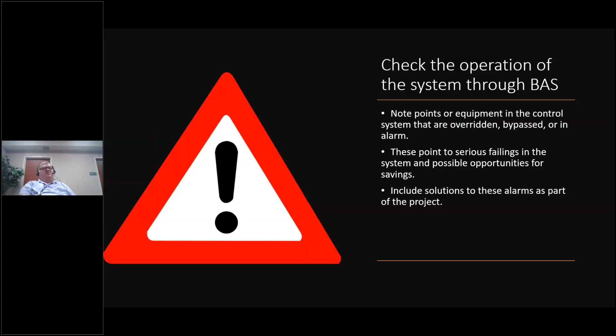Contradictions in operation: you're running 40-degree chilled water on a 30-degree day. Why? Is there any reason to do that? Why are you running 180-degree heating water on a 100-degree day? You're heating and cooling at the same time. Manual operation: units operating in hand are overridden at a fixed set point. Why? Ask the Moneyball question.